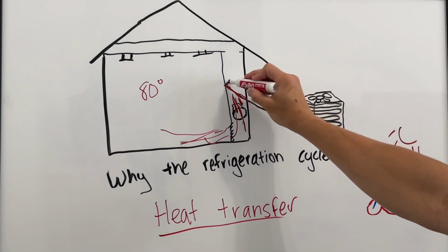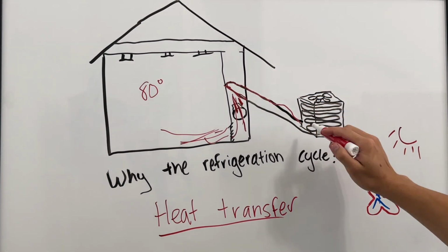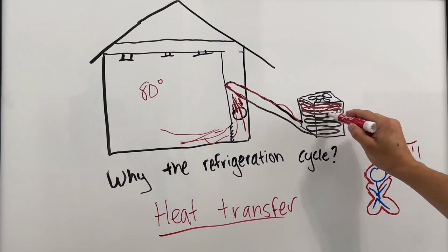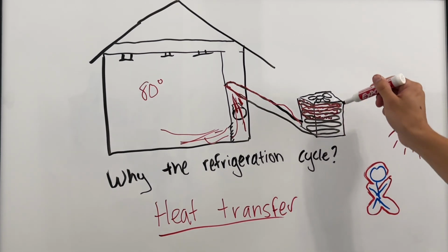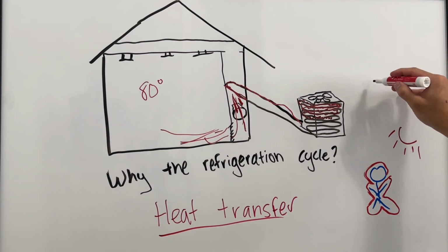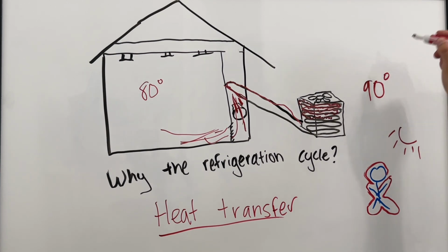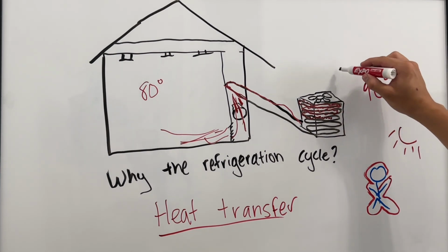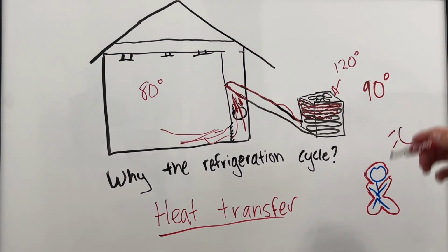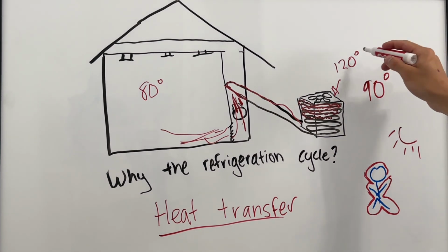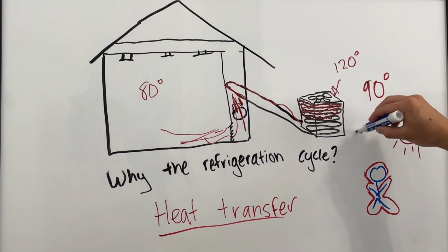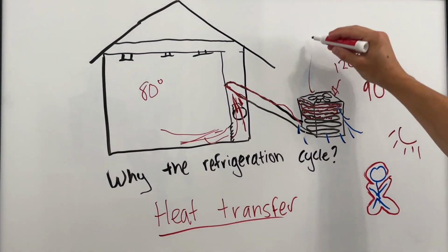That heat gets sent out to the condensing unit and to the compressor. The compressor will pump it throughout the condensing unit, and as it's going through this condensing unit, this fan is on and it's pulling the outside air, which let's say it's 90 degrees. The temperature of this vapor right now is about 120 degrees. So when we have 90-degree air blowing over 120-degree coils, since this is colder than this, it's cooling it off. So we're pulling air across these coils. We start to expel heat.